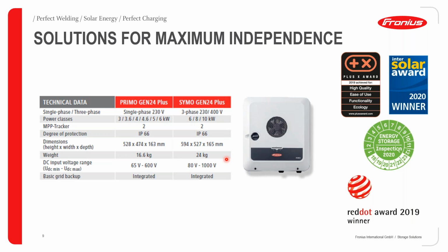In terms of the input voltage range, the Primo Gen 24 Plus will start producing AC power as long as 65 volts on the DC is reached, whereas with the Symo, as long as we reach 80 volts DC. The maximum voltage you can attach to the Primo Gen 24 Plus per string is 600 volts, whereas with the Symo Gen 24 Plus, it's 1000 volts. Okay, both of these devices have basic grid backup integrated.